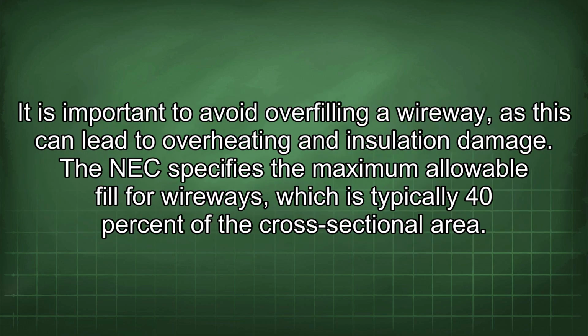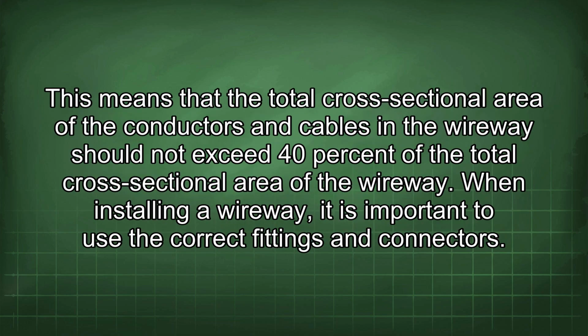It is important to avoid overfilling a wireway, as this can lead to overheating and insulation damage. The NEC specifies the maximum allowable fill for wireways, which is typically 40% of the cross-sectional area. This means that the total cross-sectional area of the conductors and cables in the wireway should not exceed 40% of the total cross-sectional area of the wireway.